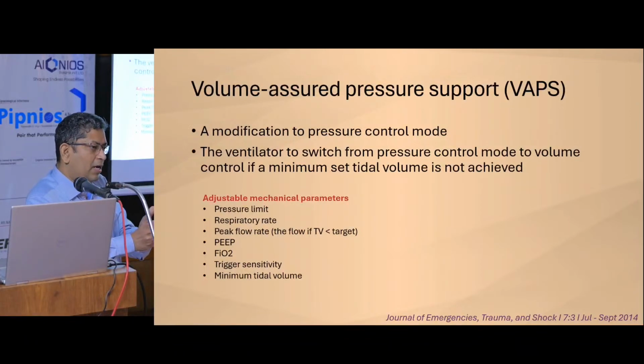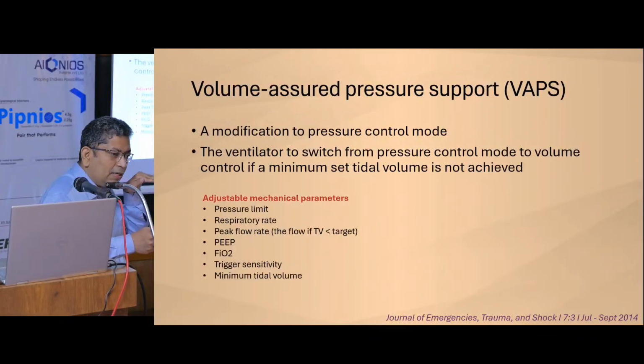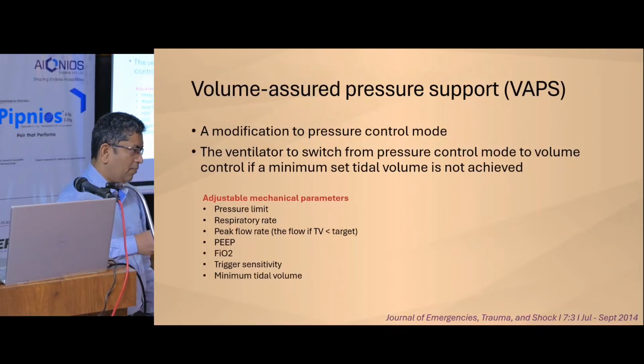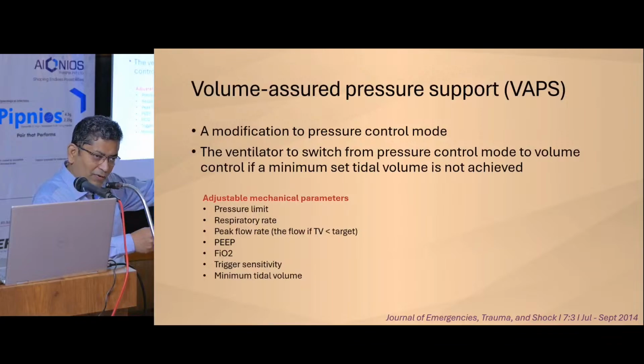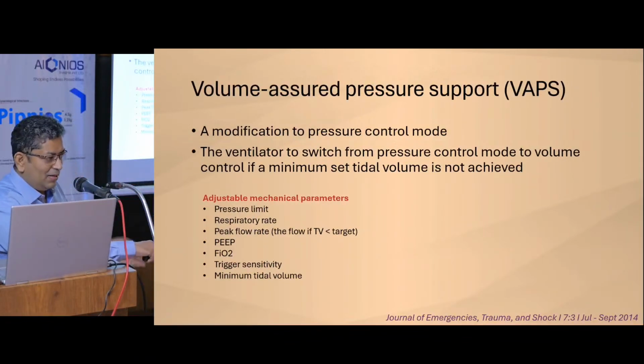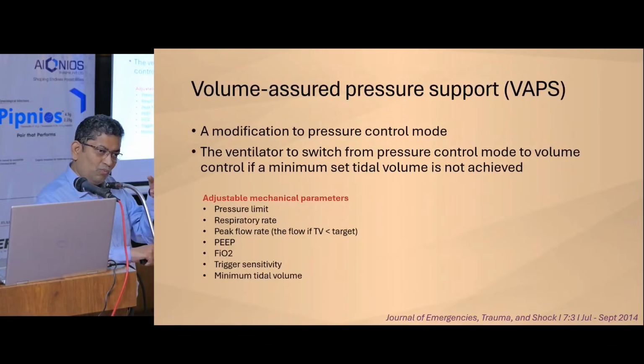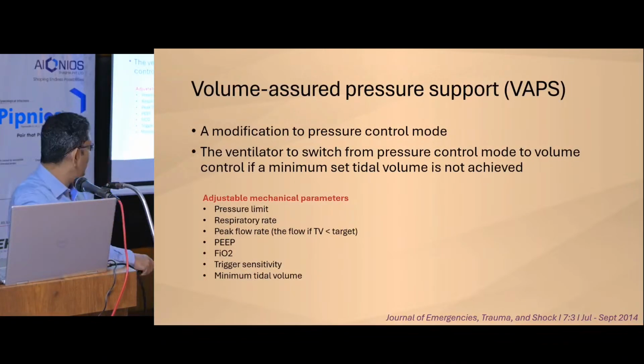The ventilator will see whether the whole tidal volume is achieved or not. You set a tidal volume. If the tidal volume is not achieved, a certain flow will be kept. That's how volume control works. Flow will be given till that volume is achieved, and only then will it cycle. If the tidal volume is achieved before that, it will cycle at that time. So it's a volume cycled ventilation, pressure control. But the limit is two: it can either be pressure limited or flow limited, and it is in one single breath. Each single breath, it will look. So if you put in a 400 tidal volume, the ventilator will deliver a 400 tidal volume. So this is volume assured pressure support.